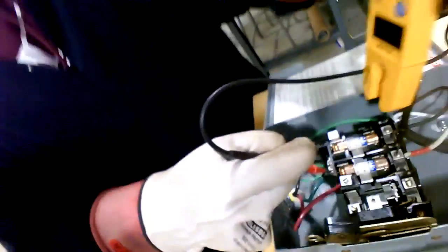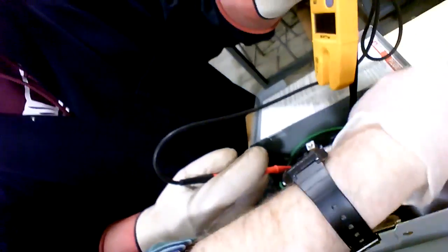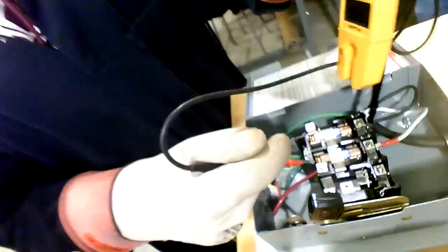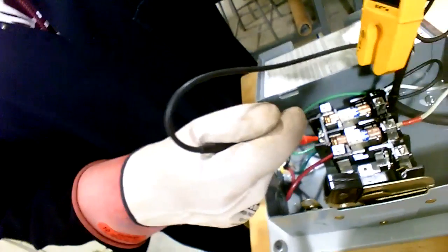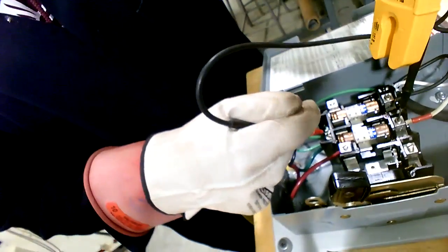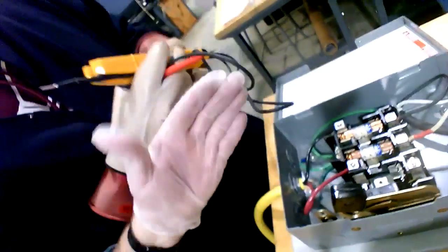Well, instead of checking top and bottom, you check across the legs coming in, L1 and L2. Zero, exactly. Now check from each one of them to ground. Right there. Exactly. Zero. Now you're fine. Now, the step to have done before that would be to make sure that the meter's good on a power source that we know is hot. So how do we find that out?